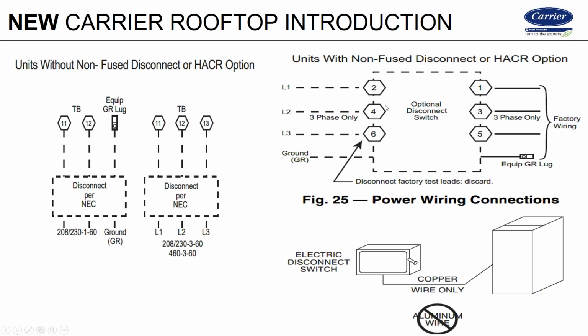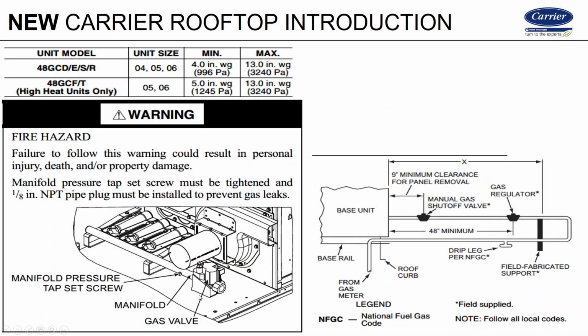Checking manifold gas pressure. They've taken the pressure tap off the gas valve, and now that pressure tap is on the manifold. On some units, the induced draft motor makes it kind of difficult to get a wrench on here to take it off. So if you have the little 1/4-inch hex socket, that's ideal to take this plug off, and you put your port on here to check your manifold gas pressure.